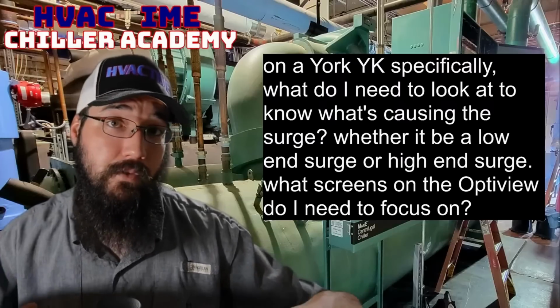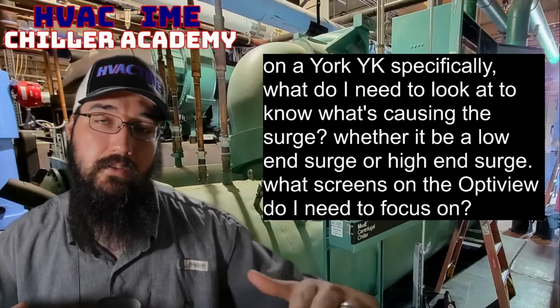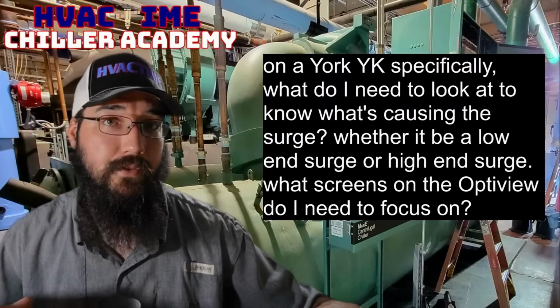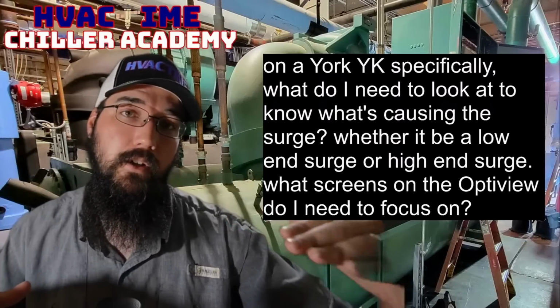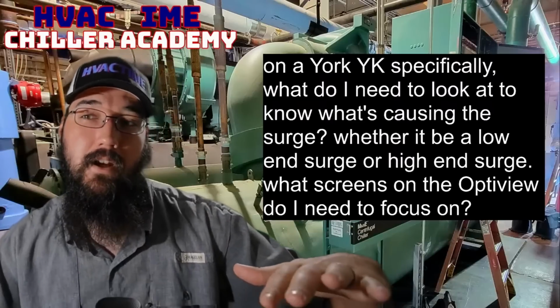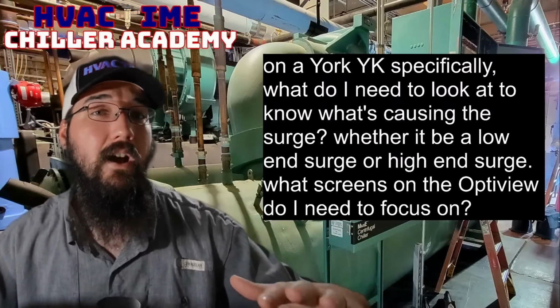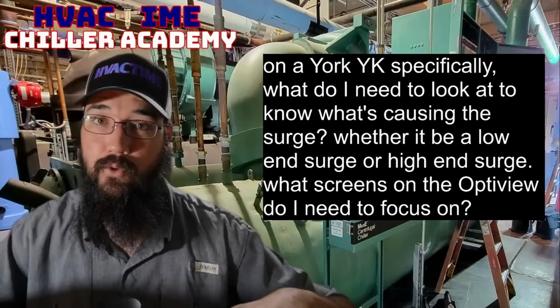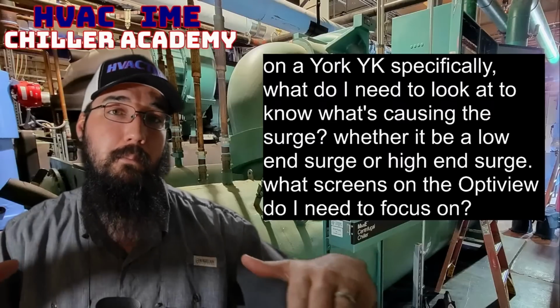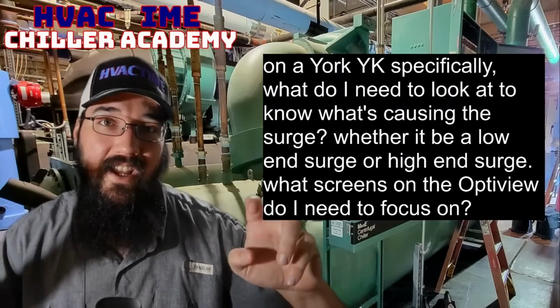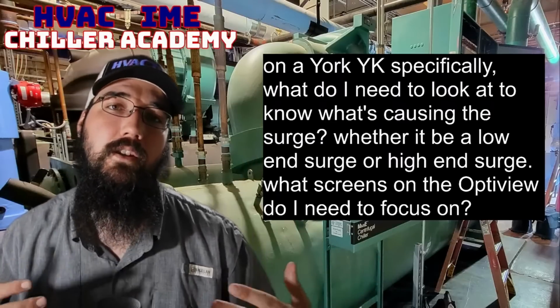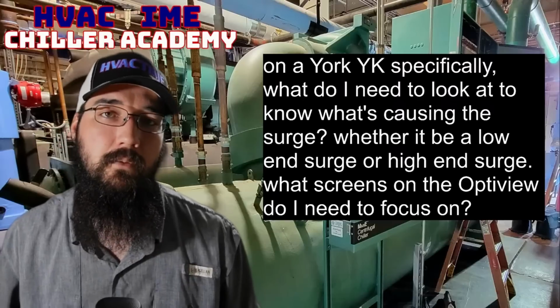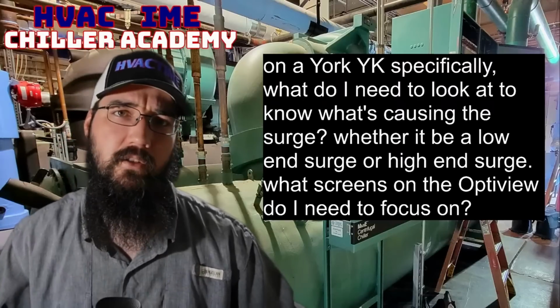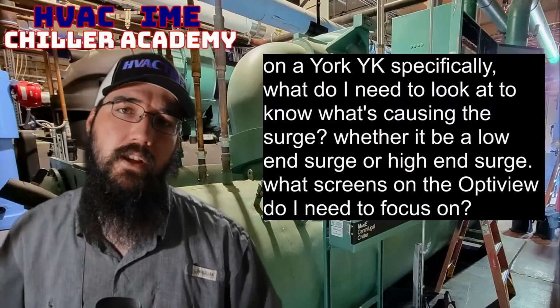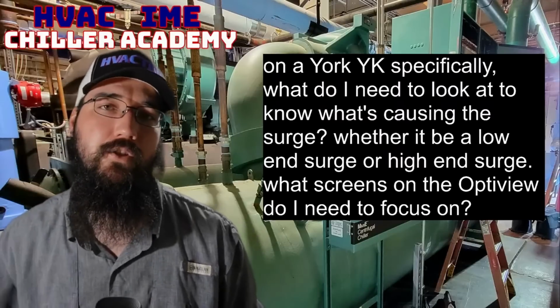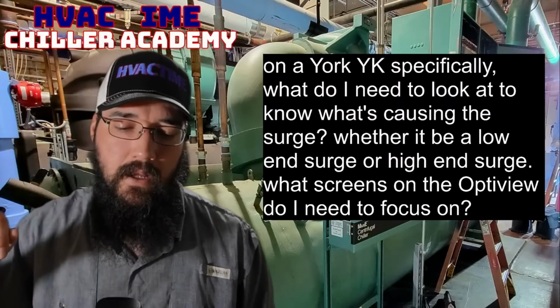The evaporator, if everything is charged correctly and running right, should be right at about half sight glass, and your condenser sight glass should be somewhere between 1/3 to 1/2. If everything is charged and tuned and running smooth, those are about the standard operating levels that the factory would expect that machine to be able to do. So all of that is correct. Then we get into a whole other, more challenging side of that conversation.